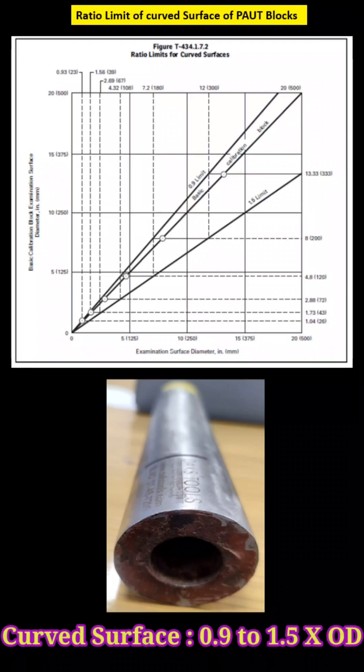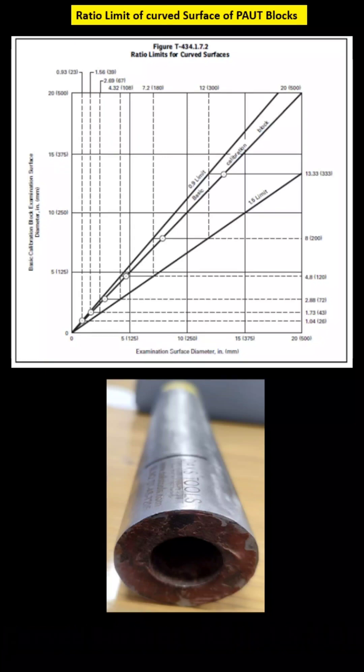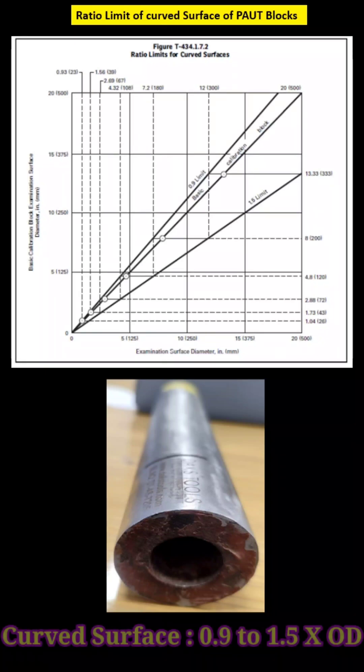But in case of boiler tube, we should require the same curvature of the block, or else there is a limit that is 0.9 to 1.5 times the outer diameter we can use.